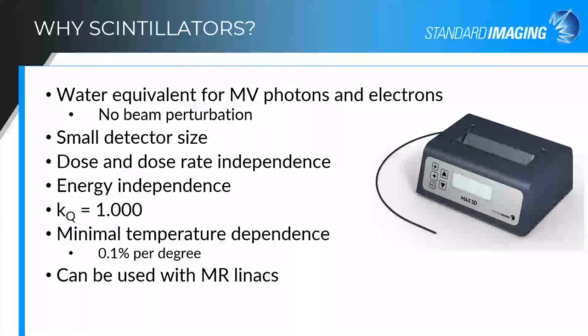There is a very small temperature dependence with this device — about a tenth of a percent per degree. So if you're using it at room temperature for QA measurements, that can generally be ignored. The other advantage is that there are no ferromagnetic materials in the optical fiber or the organic scintillator itself, so they can be used with MR-Linacs.